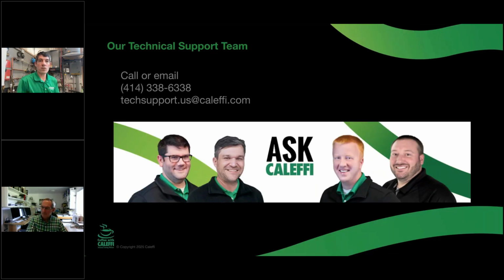One of the questions, John, you covered it, but I wanted to just double check. At the very beginning, you were talking about the short fat headers for piping configurations that you mentioned. The number that you said for sizing that, the question was, can you go up one pipe size? And I said, well, it depends. And the number that you gave was 2 feet per second, right, as if you're calculating for all of the zones to be on. So if you have like 10 3/4 zones going off of that, 1 inch wouldn't be correct in that scenario.